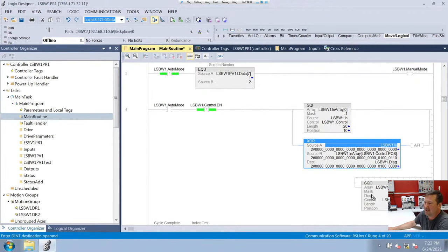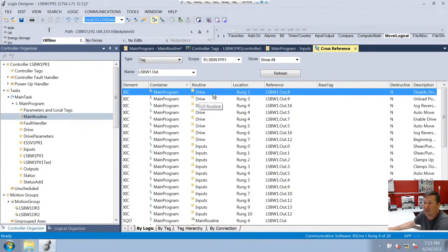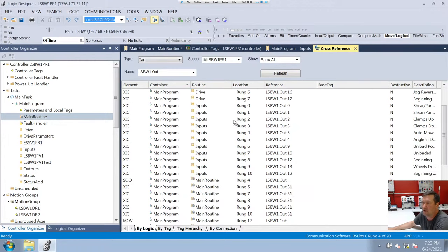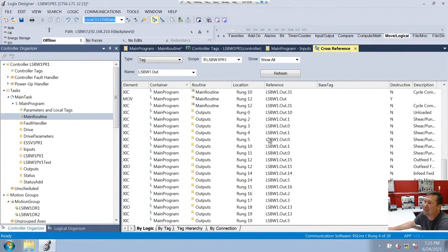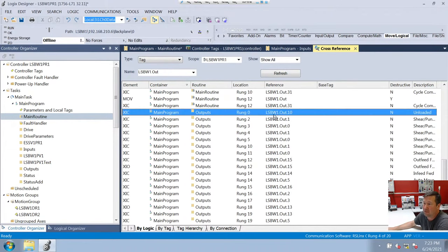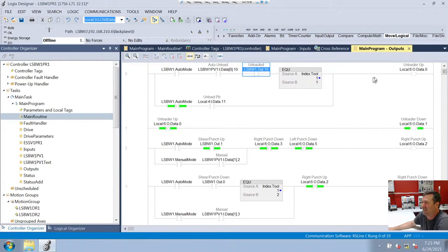If we go back to our main program, we had this destination. Let's cross-reference it. They're used in drive, inputs, main routine, and outputs. Not real clear, but I would guess if I was looking for an output it would be in the outputs. This is the first thing that kind of looks like code I would want to troubleshoot: we have an unloader, this is the unloader up, and it is going to go up if it's in auto mode.